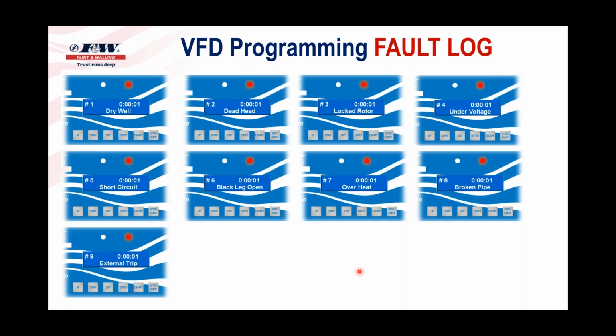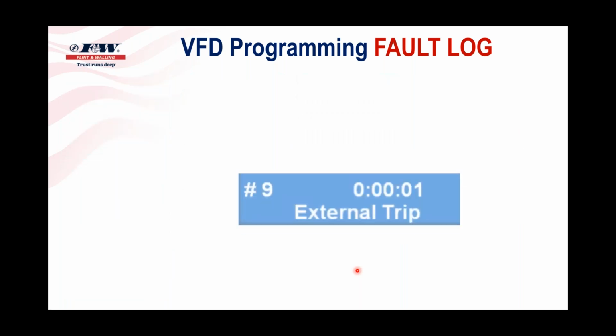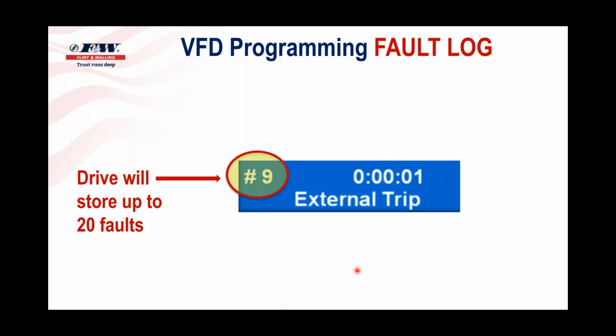And so this drive will hold 20 faults, so it'll store up to 20, and they're all in numerical order, as you can see here. Once all 20 are filled up, that may or may not ever happen, but once all 20 are filled up, you get nuisance tripping going on, like the guy with the broken pipe. He was getting 1 or 2 a day. But once they fill up, then when the new one comes in, it takes the number 1 spot. Everybody else moves down 1, and number 20 goes off the screen and goes away. So it only stores the last 20 faults.